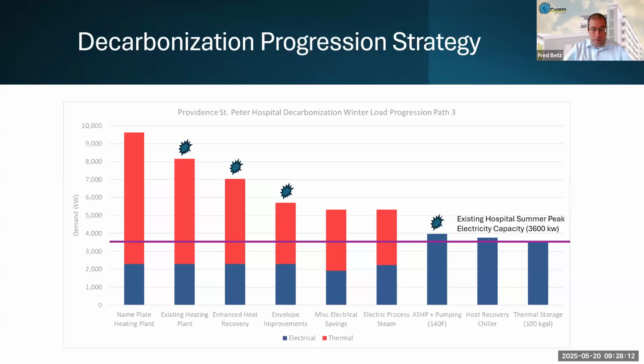The next challenge that is often pointed out is the capacity of heating. So you can see that big red bar on the left is the nameplate heating capacity. And this is what people will look at and say, look, our heating plant has this capacity. There's no way we can electrify this. And this is where we really, really start getting into data. And a lot of this is data driven. And it's actually the single advantage that existing facilities have over new construction. Because new construction, and I've designed lots of new hospitals in my career, ultimately it's an engineered guess, right? But we all know that the actual performance does not always align with the projected performance.